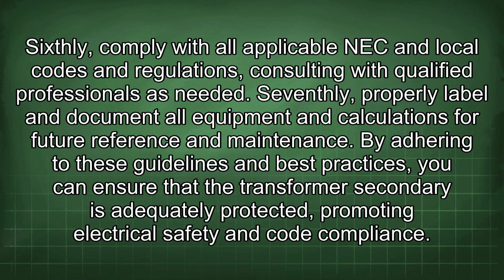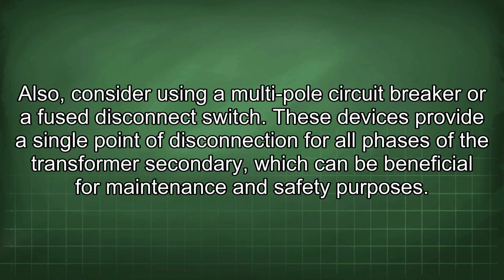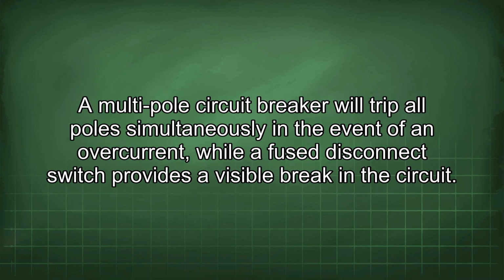Also, consider using a multi-pole circuit breaker or a fuse disconnect switch. These devices provide a single point of disconnection for all phases of the transformer secondary, which can be beneficial for maintenance and safety purposes. A multi-pole circuit breaker will trip all poles simultaneously in the event of an overcurrent, while a fuse disconnect switch provides a visible break in the circuit.